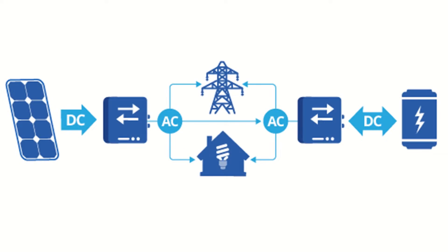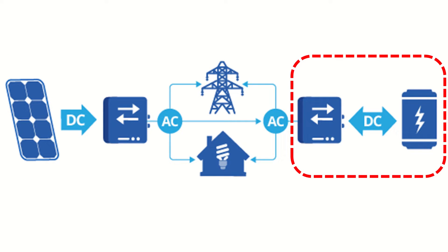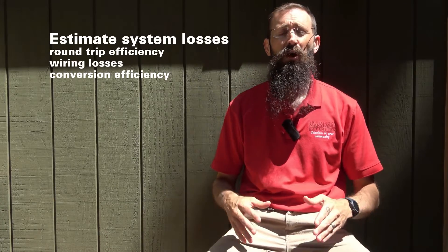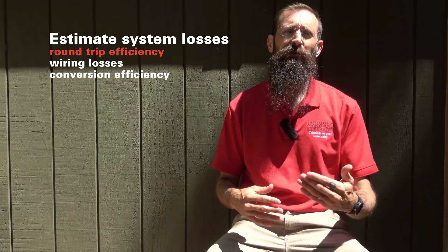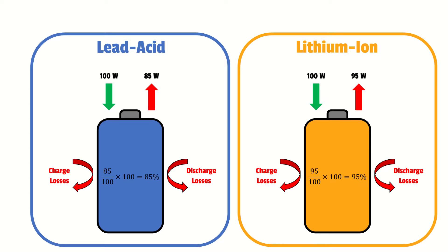Before determining battery bank size, we'll estimate system losses. In today's video we focus on load subsystem efficiency, including round trip battery efficiency, wiring loss, and conversion efficiency. Since no battery is 100% efficient, we use a round trip efficiency factor to measure energy retention after charging and discharging. The round trip efficiency for a lead acid battery is commonly around 85%, while lithium ion batteries are commonly around 95%. These loss estimates are based on the chemistry of each battery — lead acid batteries typically operate with lower electrical currents and take longer to charge.